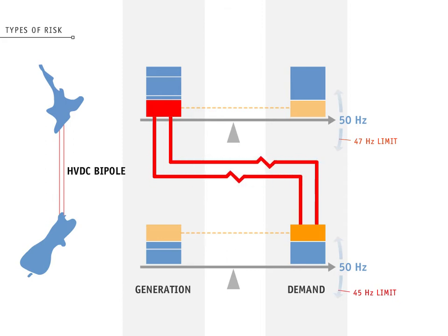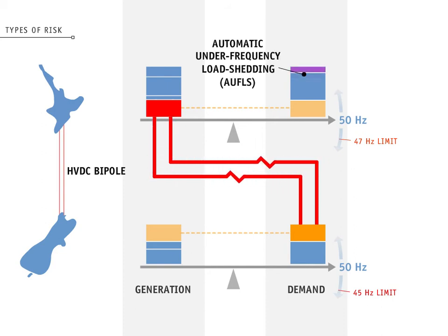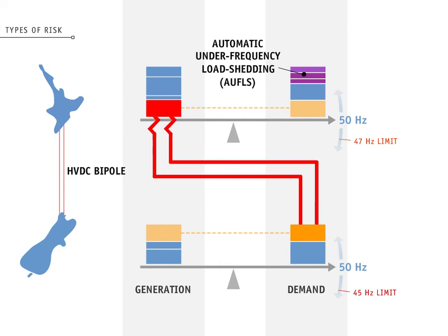DC-ECEs are also called bipole trips. When they happen, our reserve management tool has already calculated the FIR and SIR needed to prevent cascade failure. The reserve calculation for an extended contingent event, or ECE, includes automatic under-frequency load shedding, or AUFLS. This automated shedding of system load is an addition to the interruptible loads.